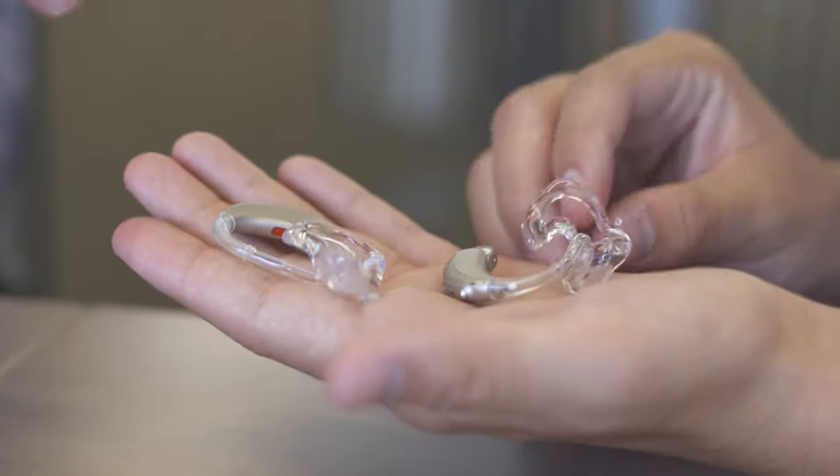So what's the big difference between these and the Marvels, which are behind the ears? The Marvel product we have now is the Audeo M, which is the RIC device. That's another example of a RIC type device — the electronics package sits behind the ear. In a RIC or BTE type product, those electronics are kind of predefined, mass produced in some ways where all the electronics are in one package. With custom products, not every ear is the same, so if someone has a very narrow ear canal or a tight bend, those electronics aren't going to fit exactly the same. You have to figure out how to slot the different pieces in there.